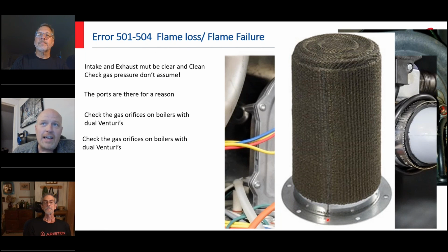You guys all have a shop vac, so you know that over time you suck in all the dirt, it sticks to the filter. Well, the boiler's a shop vac in reverse. We blow all the clean air into the center of the filter, which happens to be your burner, and all the clean air comes out and all the dirt stays inside. So they can and do get plugged up. Airflow, number one.